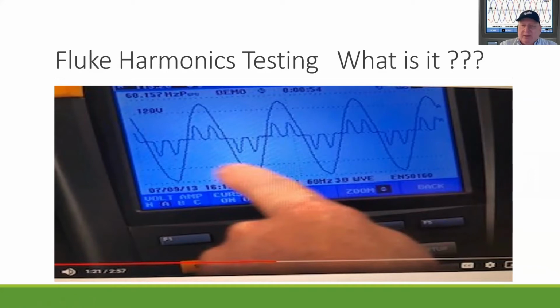And so you get what they call voltage harmonics. It's very important to understand they will vary depending on the transformer, the load, and the motor load. But I just want to give you a little bit of understanding of what it is, because a lot of people say, oh, you've got to put a harmonic filter on, and so on. It's really about understanding where they're coming from.